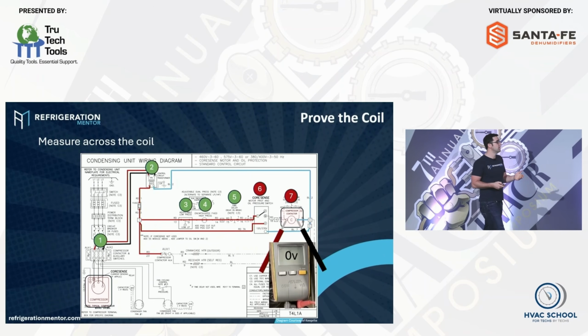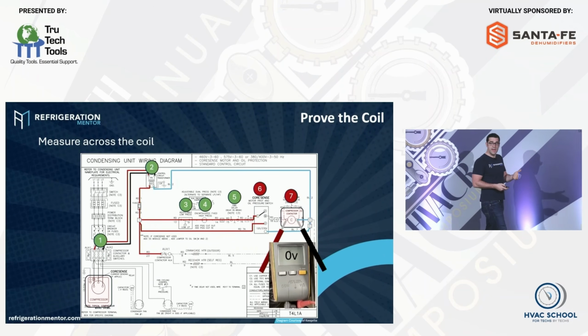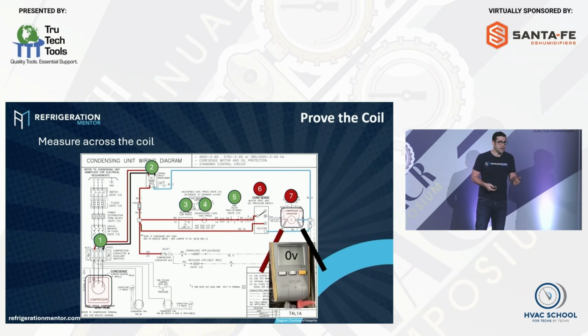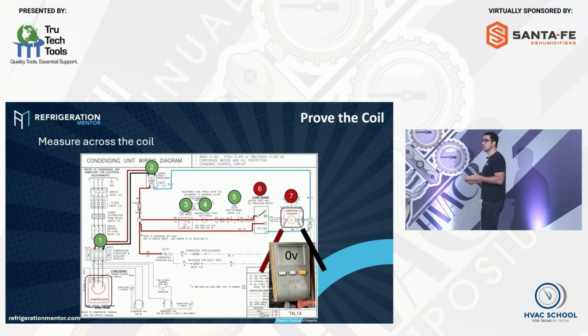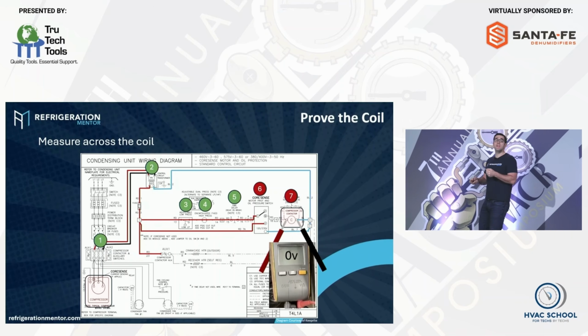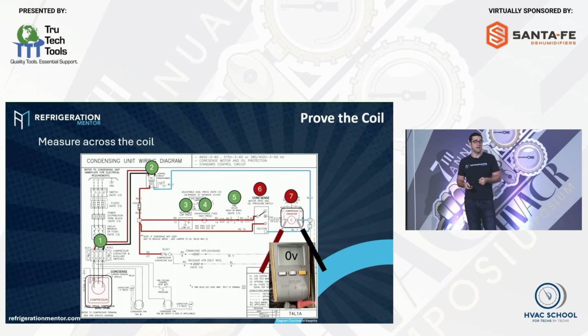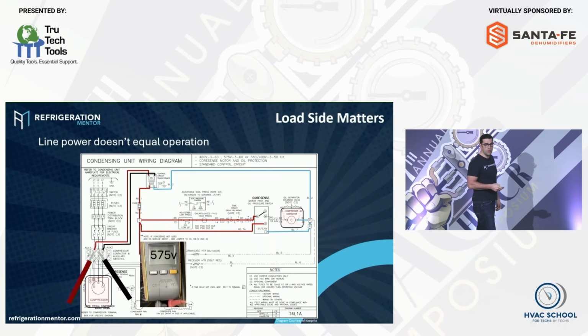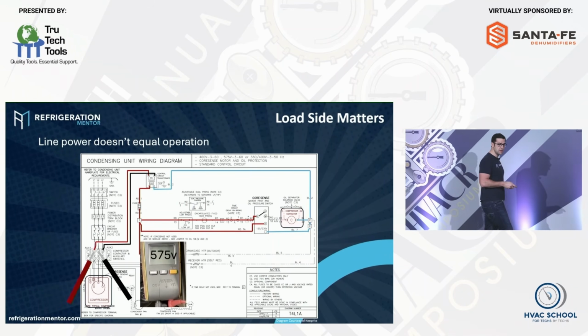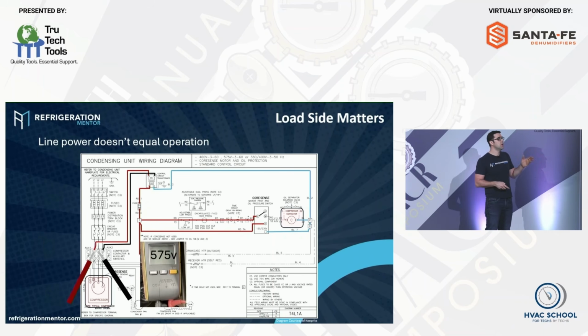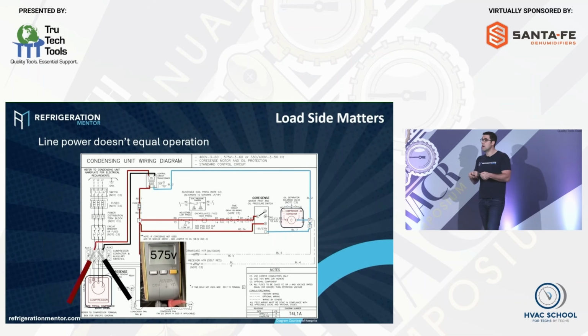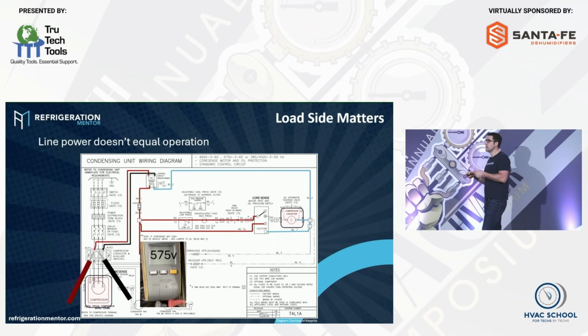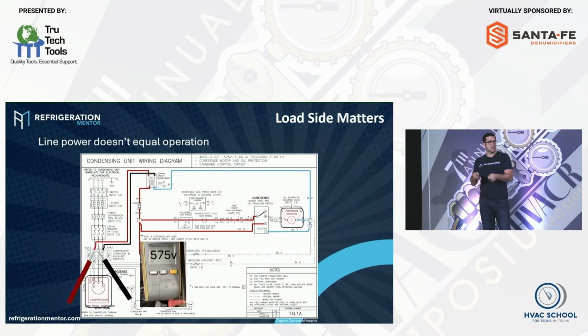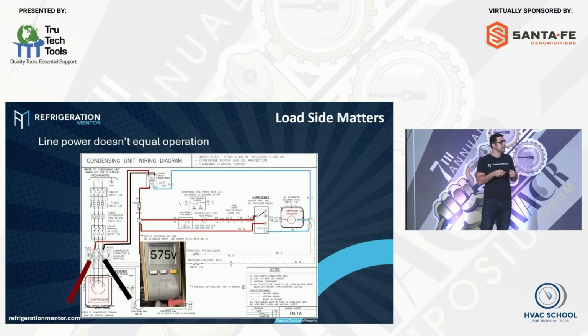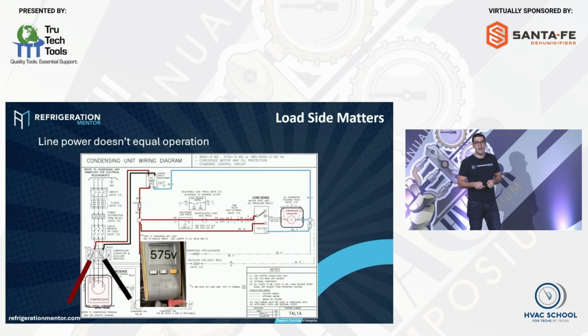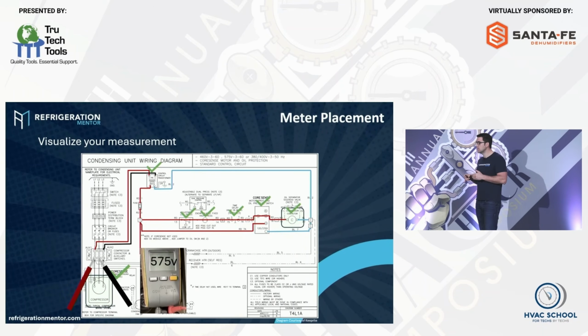We go upstream. If we take a look at this example, we have a tripped oil pressure control. This is just an example, but we've got to go upstream before it if we don't have any power there. Okay, it's so important to prove it. Load side matters. So line power doesn't equal operation. Just because I've got line power, I have my 575, my 208, 230, my 600 volts, my 460 volts on the line side, it doesn't mean that we've got load power at this time. Meter placement is so important.